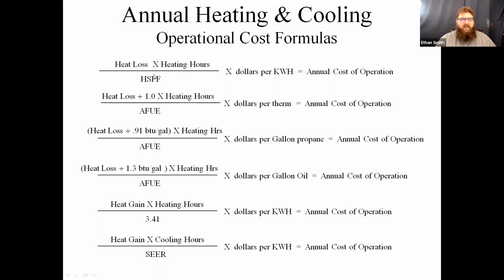And the HSPF comes from your unit data. Dollars per kilowatt hour: most electric utilities are going to bill in kilowatt hours, so you don't have to do any conversion there. You just need to find out what your dollar per kilowatt hour is. I like to factor in taxes and connection fees into that because that gives you your total annual cost of operation. But if you just put the numbers in as they're listed, you'll come out just fine. I've got a couple examples of this later on.